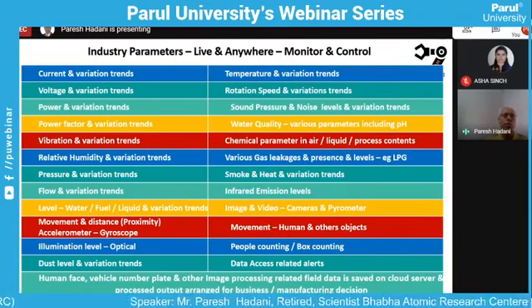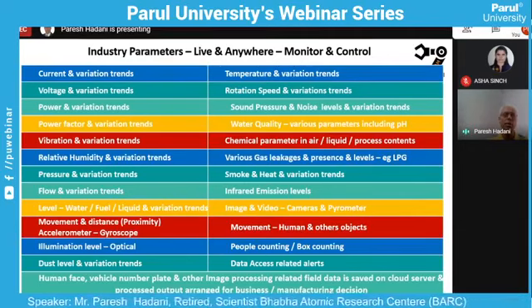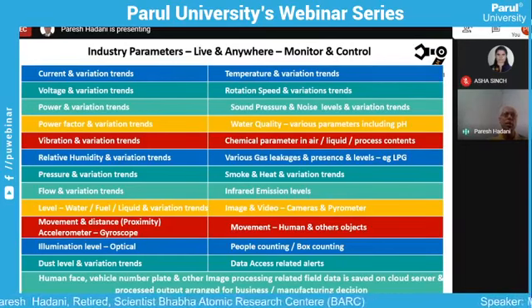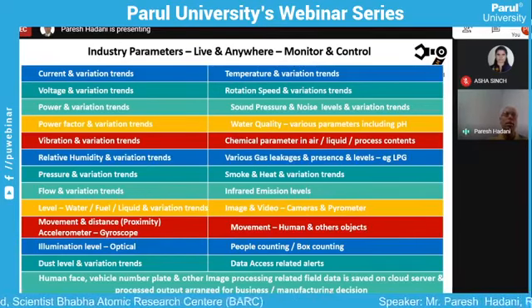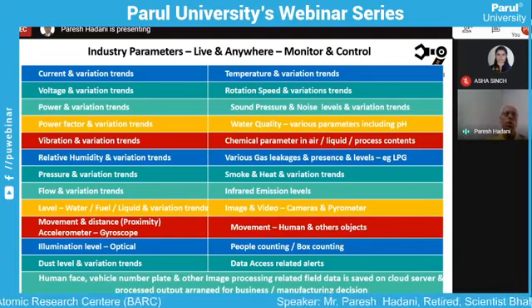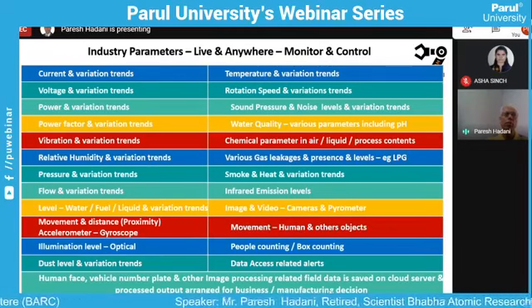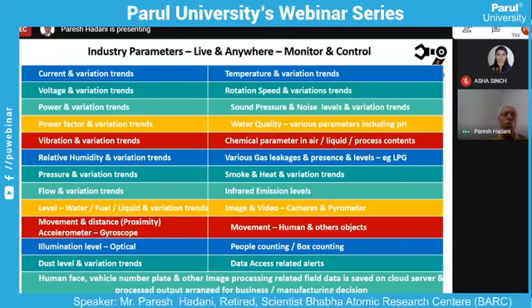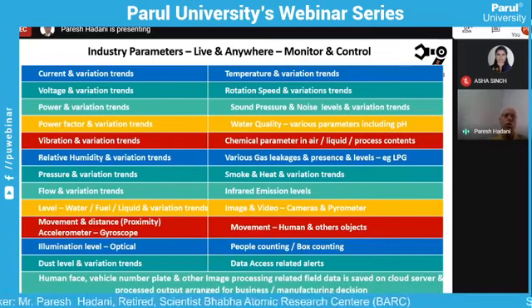Now, let us say a few motors are driving our machinery, and one motor is consuming, let us say, 15 ampere current in a regular way. Now, when the bearing starts deteriorating or the motor is aging, the current consumption will get disturbed and the motor will start drawing more current - let us say 16 ampere, 17 ampere. The motor will not stop working, but if you do not correct the problem or do the preventive maintenance, a time will come when the motor will try to consume double the rated current and it will fail. And once the motor or a particular equipment fails in the industry, it will stop the complete production line and have a huge loss or financial impact.